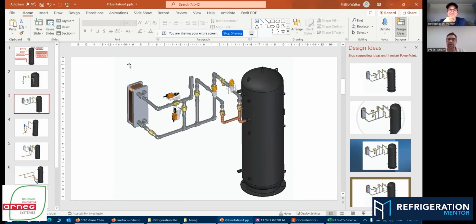Yeah, and it's becoming more and more popular. We're working on a design right now where we're going to have an internal, quote unquote, type of chiller. There's a large freezer floor that will be warming, and that temperature coming back from the freezer floor, we can manipulate not only to provide heat recovery for the freezer floor, but to serve internal means within the refrigeration system. Wow, that's so awesome. Subcooling, we can subcool it, we can cool it, we can heat. It's another point of all this that we just spoke about with mass flow.